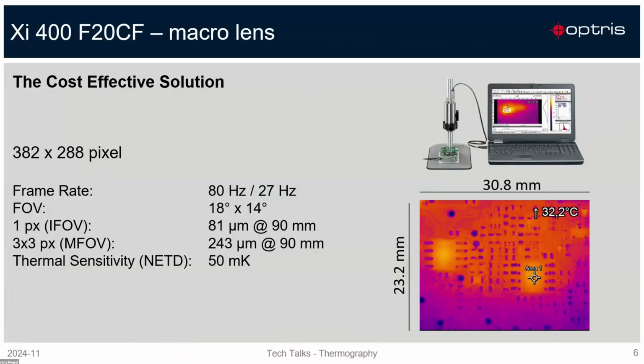Yeah, especially for different applications, we have developed suitable types of microscope optics for the infrared cameras. And yeah, one cost-effective solution can be here the XI400 camera with a macro lens. The XI400 has a resolution of 382 × 288 pixels, and it has a frame rate of 80 Hertz. So it's a very fast solution also. You have here a field of view of 18 degrees × 14 degrees as optics, and 1 pixel size can here go down to 81 microns. So this is at a distance of 90 millimeter.